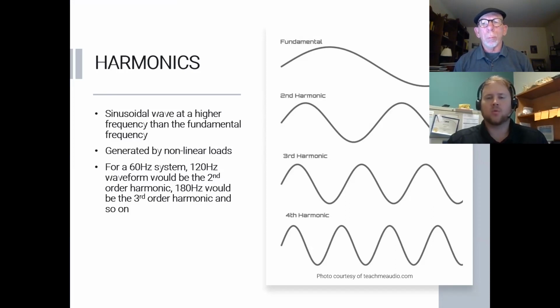Well, where do harmonics come from? They're generated by nonlinear loads like VFDs, variable frequency drives, electronic devices, rectifiers, even, in some cases, LED bulbs, if you've got enough of them, maybe in a commercial building. Harmonics can cause your equipment to overheat, nuisance tripping on the circuit breakers, and then, of course, distortion of the base main supply voltage.